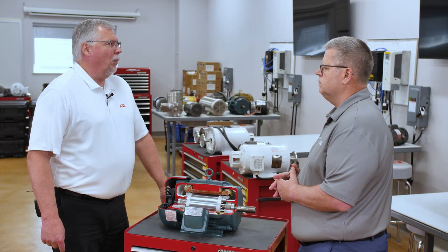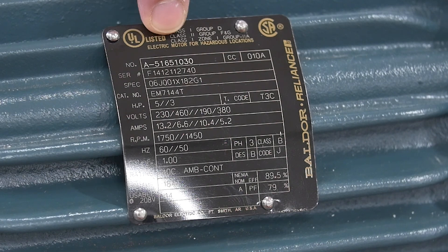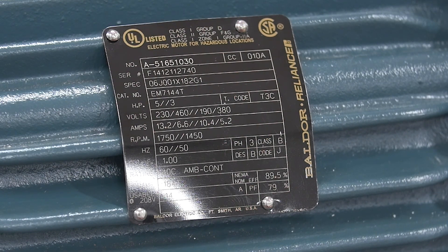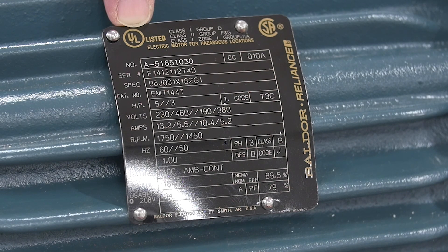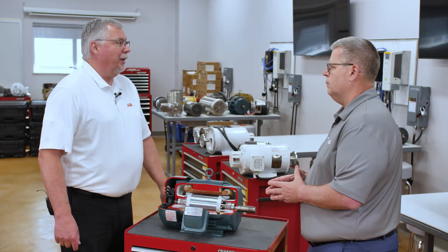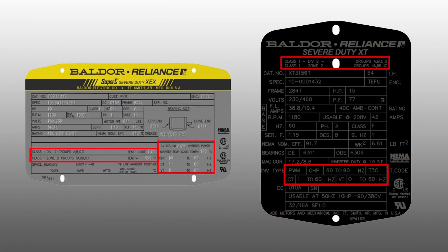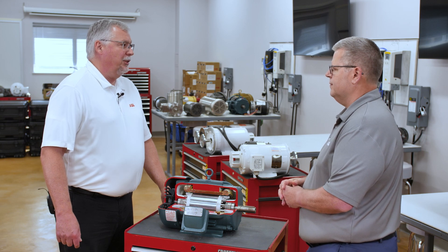The best way to identify a hazardous location motor is by the nameplate. For a Division 1 motor, the nameplate will most likely clearly state 'electric motor for hazardous location.' It will also show UL listed, indicating Underwriters Laboratory Certification, and list the classes and groups identifying the hazardous area where it is approved to operate. One thing you will not find on a Division 1 motor nameplate is the Division classification, because the Division 1 motor is suitable for both Division 1 and Division 2 areas. For Division 2 motors, the nameplate will have Division 2 classification marks and will clearly state Division 2, as the motor is suitable only for Division 2 areas.